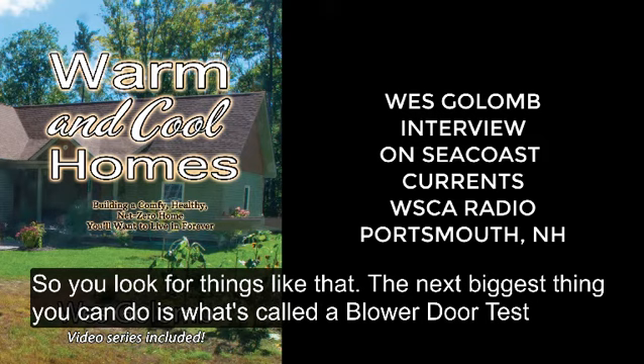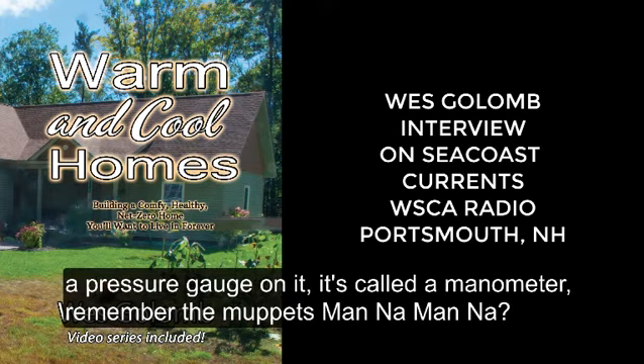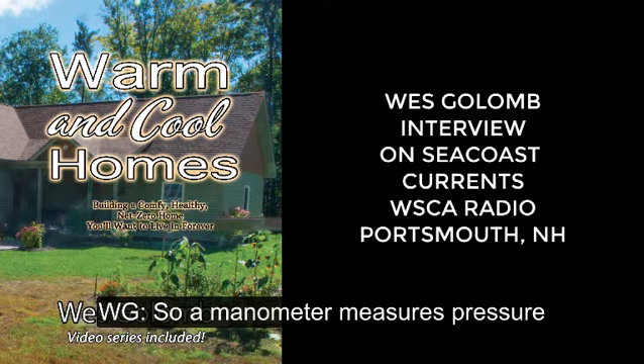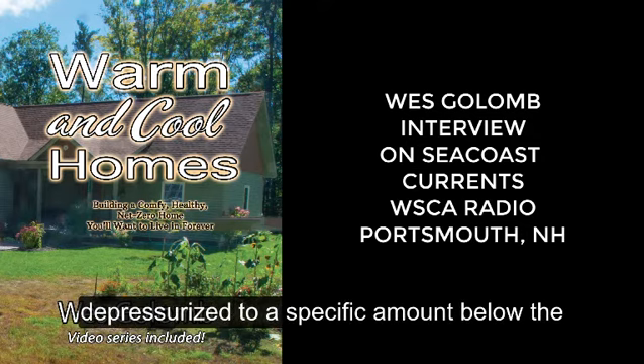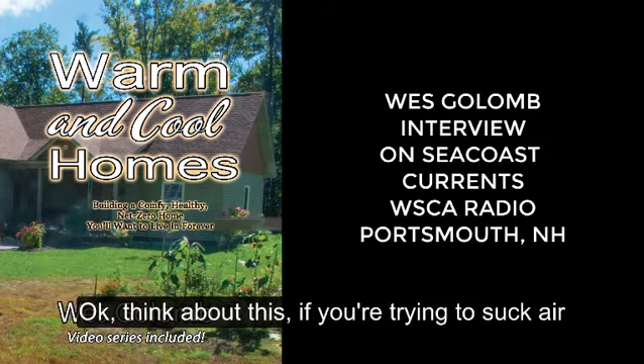The next biggest thing you could do is what's called a blower door test. A blower door is a huge fan with a pressure gauge on it. It's called a manometer. Remember the Muppets Mahna Mahna? Yeah, it's a good way of remembering it. So a manometer measures pressure. And what this fan does is it depressurizes the house. The idea is to get the house depressurized to a specific amount below the outside, and then you measure how much air is being sucked through.